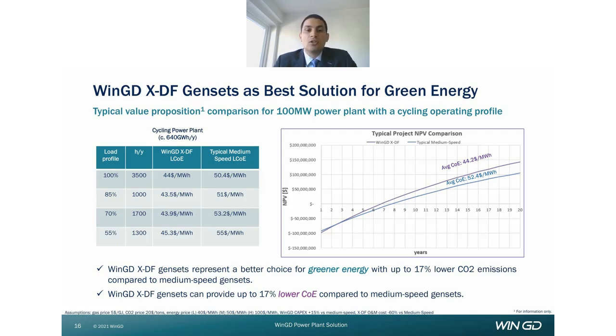Such 17% lower cost of electricity for this particular operating profile can be easily translated into up to $6 million per year in overall saving from a power plant's owner perspective. The high efficiency that we discussed in the previous slides is translated into low CO2 emission. In this particular case that we are discussing, it means 17% lower CO2 emissions compared to a typical medium speed genset. These are the 2 main takeaways I would like to bring to you from this presentation. With this, I conclude my presentation on the benefit of the XDF genset for power plants application.